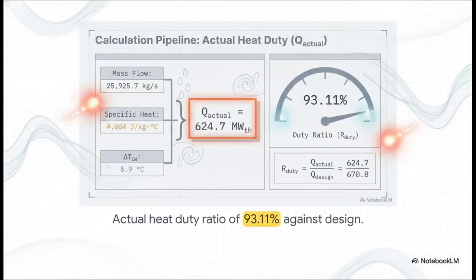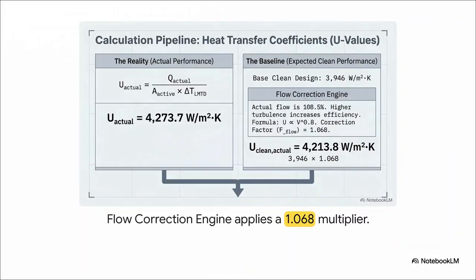Next, we calculate the actual heat duty. Basically, how much raw thermal energy are we actually moving? We take that highly accurate mass flow we figured out earlier, combine it with the specific heat of our rainy season seawater, and multiply it by that cooling water temperature delta of 5.9 degrees. The result? 624.7 thermal megawatts. When we compare that against the design duty, we get a duty ratio of 93.11%, which means the plant is efficiently rejecting the exact amount of heat required for the current load. Perfect. Now for the most critical math of all.